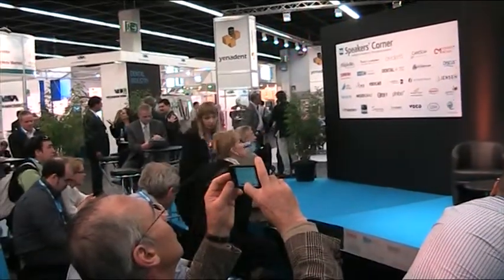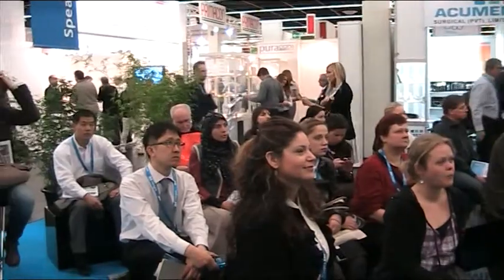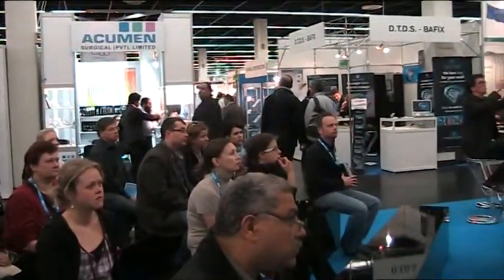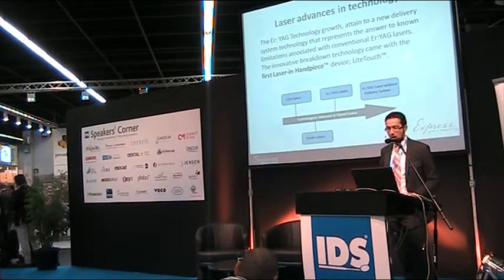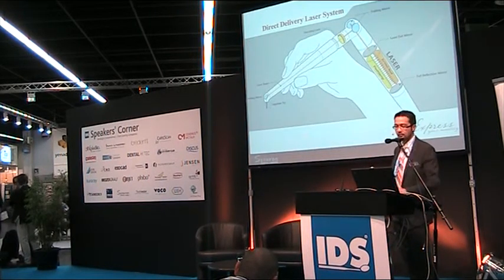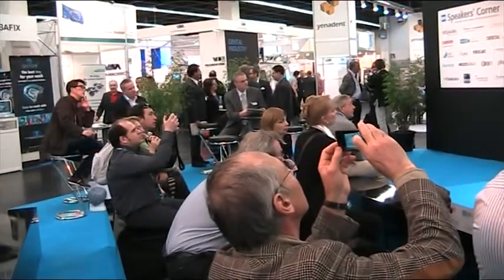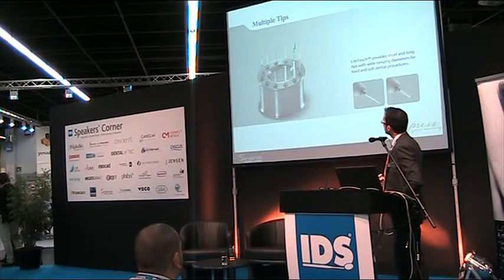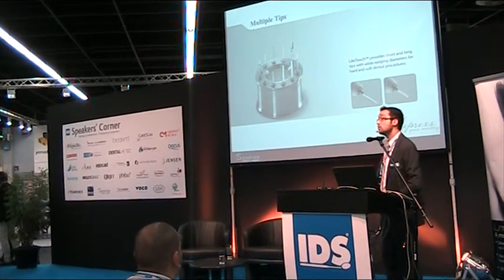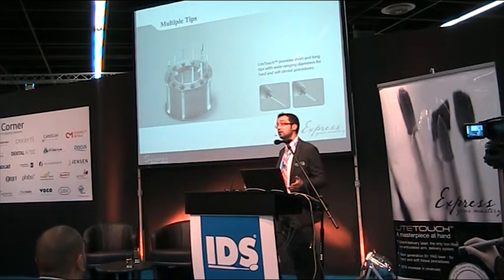Another limitation is that fiber delivery systems are fragile, breakable, and very expensive. The advance in laser technology today is this: the first unique laser in the world with no optical fiber. The laser is housed in this chamber, and the optical system uses only some reflecting mirrors — known as the LiteTouch first laser handpiece. The system also has different rigid sapphire tips with different diameters and lengths for various cases.